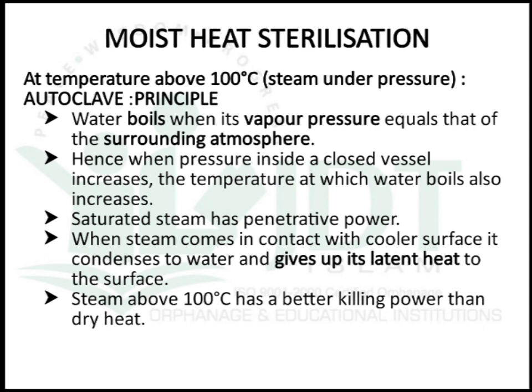Above 100°C, we use moist sterilization under pressure, with the equipment called an autoclave. The principle is that water boils when its vapor pressure equals the surrounding atmospheric pressure. At normal atmospheric pressure, this is 100°C. If we increase heat beyond 100°C, the boiling point of water does not change. To increase the boiling point, we change the atmospheric pressure by keeping water inside a closed vessel, thereby increasing atmospheric and vapor pressure.